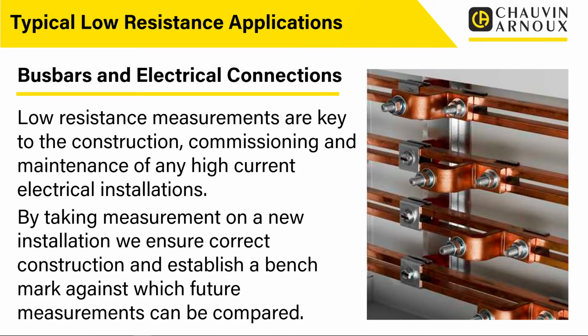be compared. So you can imagine, if we're constructing this busbar system, we can take resistance measurements to make sure that we've got very good copper to copper connections between the two. Because if you look at these under a microscope, there isn't necessarily a flat surface where these things mate. We might have a burr, we might have some contamination, some dirt or whatever trapped within the connection.